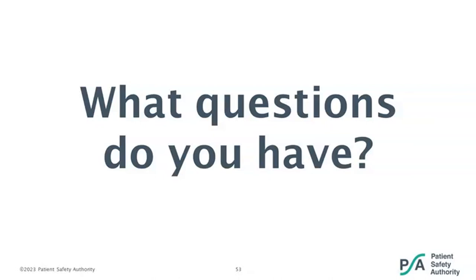The webinar is going to be ending soon. Megan, one other question: how often do you update your smart pump library? That's updated on an ongoing basis. Historically we started with about quarterly updates, but during the pandemic we recognized that updates were needed much more frequently — sometimes as often as monthly, as new medications are added or existing settings need to be updated. We no longer have a defined rigid schedule. We do have a planned communication pathway so nursing is notified in advance when library updates are going to occur, in case they need to restart the pumps or take other action.